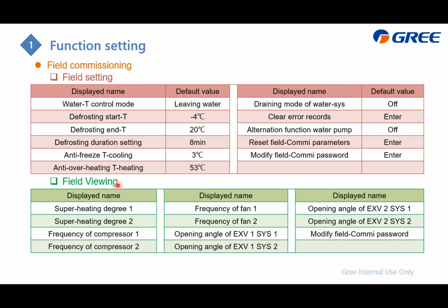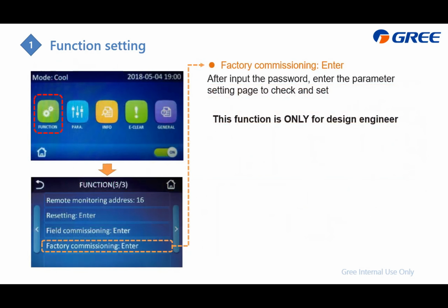And here is for the field checking. It will display all the parameters we detected, either from the compressor and fan motor, this is the RPM, and also the superheat and the EXV opening degree, ESV1 and ESV2. Last at the function page is the factory commissioning setting, but this one is only for the engineer, which is for the development. For the after sales it is no use.